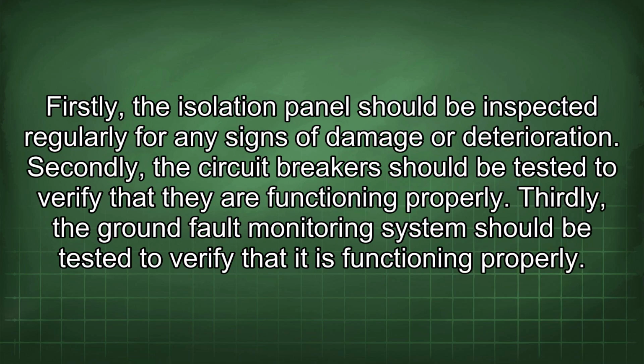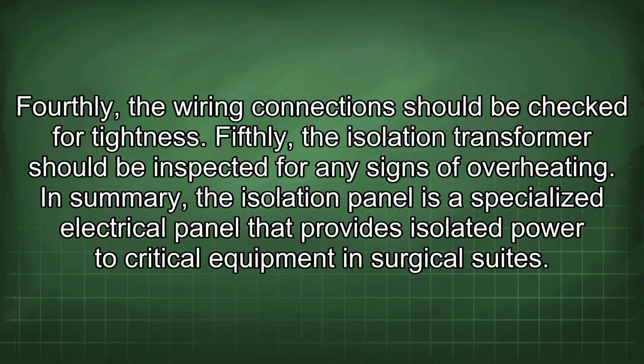Firstly, the isolation panel should be inspected regularly for any signs of damage or deterioration. Secondly, the circuit breakers should be tested to verify that they are functioning properly. Thirdly, the ground fault monitoring system should be tested to verify that it is functioning properly. Fourthly, the wiring connections should be checked for tightness. Fifthly, the isolation transformer should be inspected for any signs of overheating.